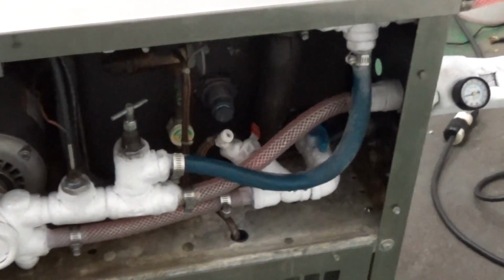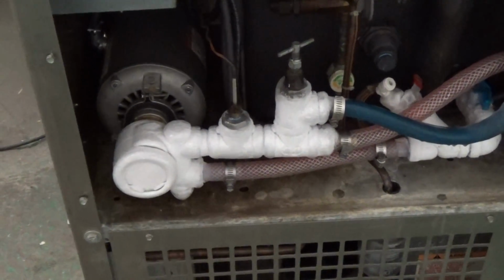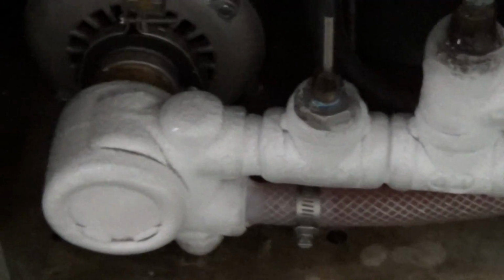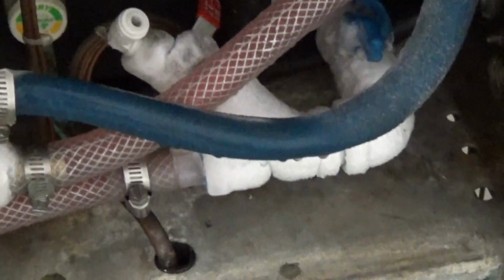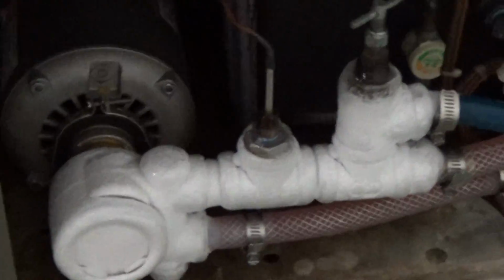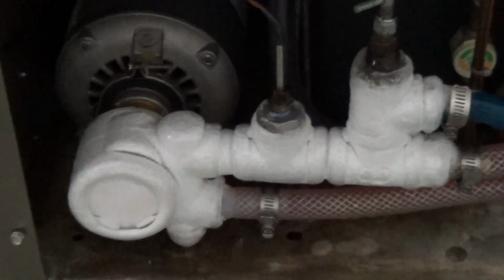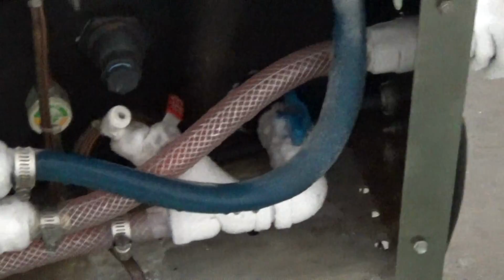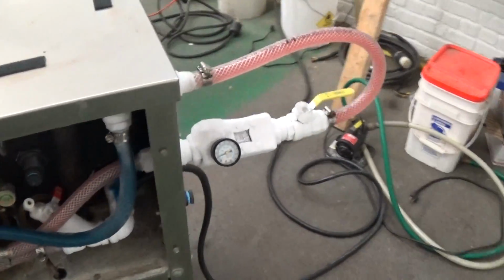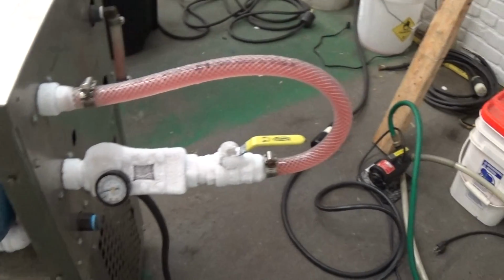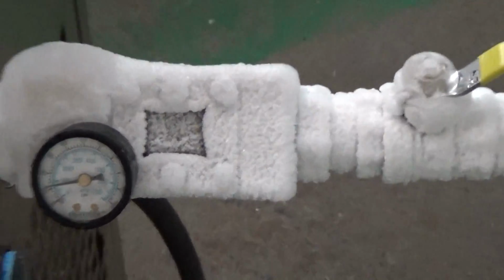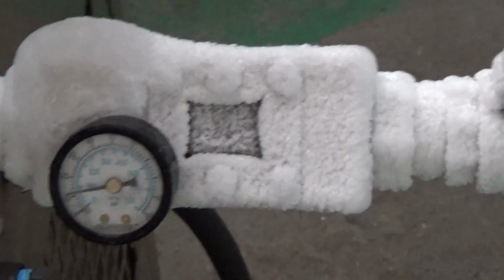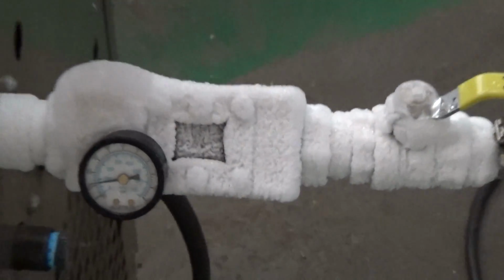On the frost issue, later this afternoon, after these videos are done, these components here, which are all new, all these fittings here are new stainless fittings and a brand new pump installed. And we even put in a little Y strainer right there. All those fittings are brand new, including that hose. But all this is going to be insulated later today after we get the frost off and defrost the unit. We've been running it just through a basic little loop here with a shut off. And that's a flow meter there to assure that the pump is working with appropriate flow. That's ours.